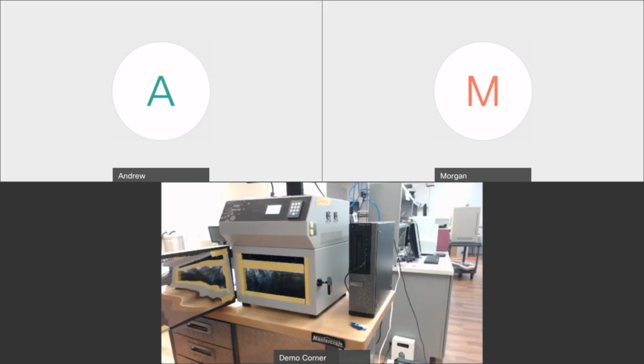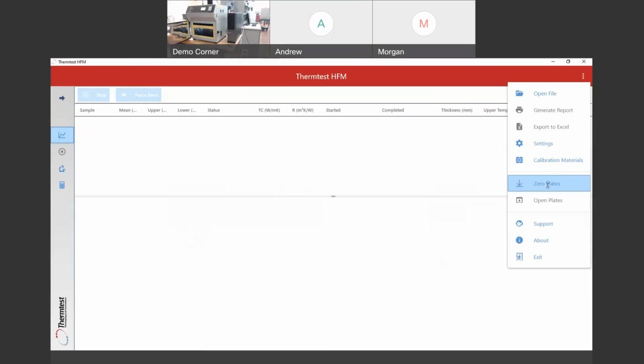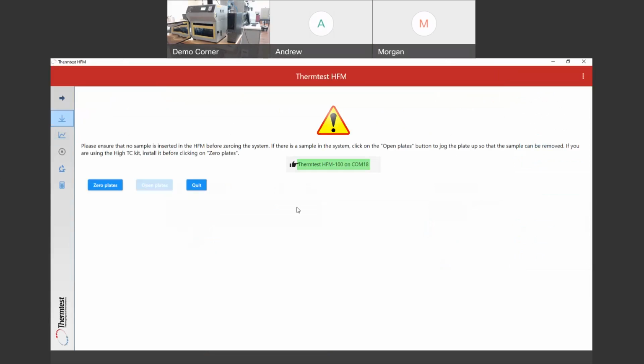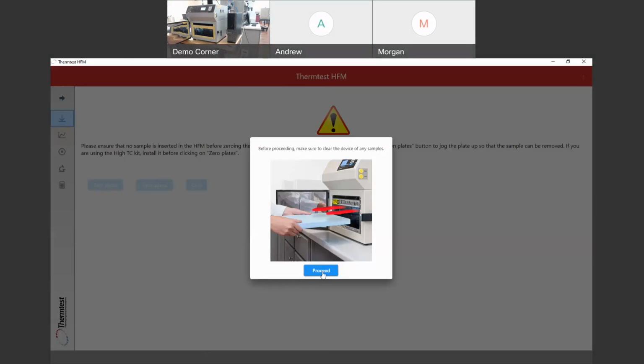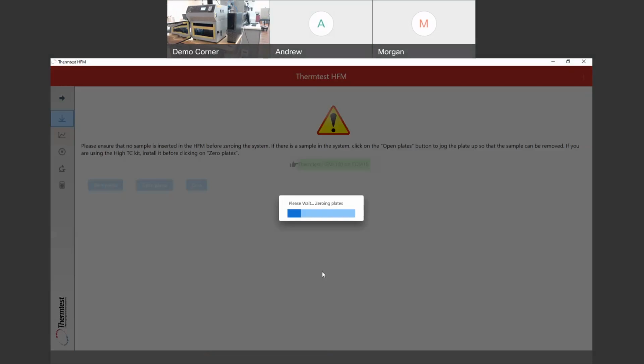All right, so I'm going to share my screen. When you first turn it on, when you first double click, you'll have this screen come up when you load your software. Can you see that screen? Yep. Okay, it'll say zero plates, and make sure there's nothing in it. That's your first measurement of the day, if you will. This is just an image to remind you that there's nothing in it, so that it's actually zeroing on 0, and it will automatically go down, pass and read a 0 for the 4 optical sensors and record that as its 0 position.